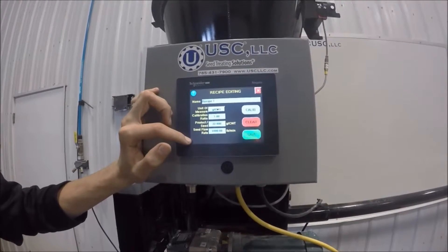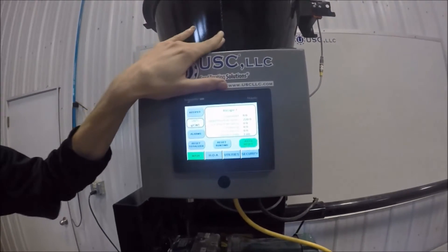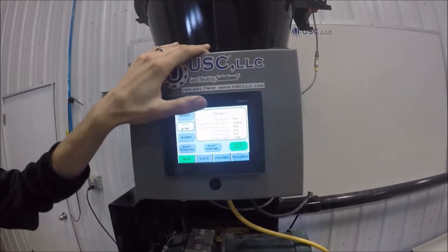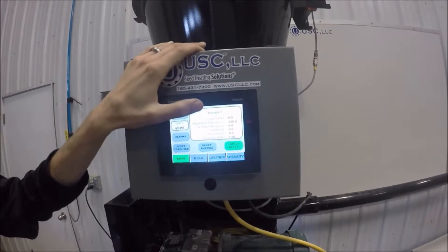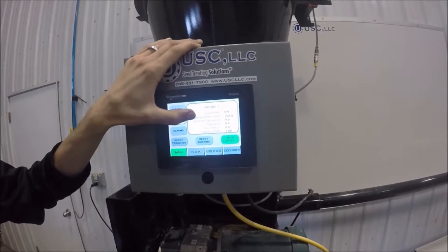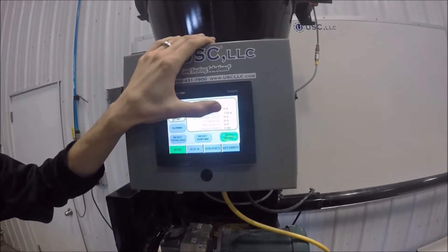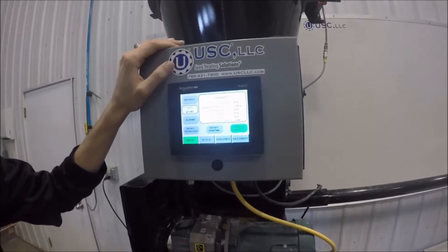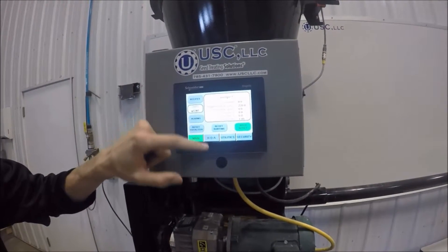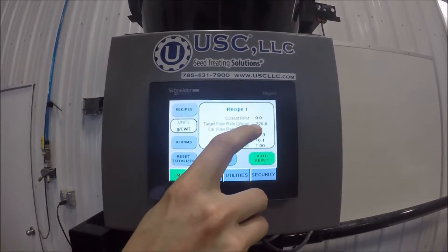Once this is set up, we can go back to the main screen. On the main screen you'll see current RPMs — this is the RPM that the motor is currently running — followed by target flow rate, which is the information we set up under the recipe. So 22 grams per hundredweight times 1,000 pounds per minute gives us 220. Next is calculated flow rate, which shows how fast our dry auger feeder is running compared to the flow rate we want to achieve.